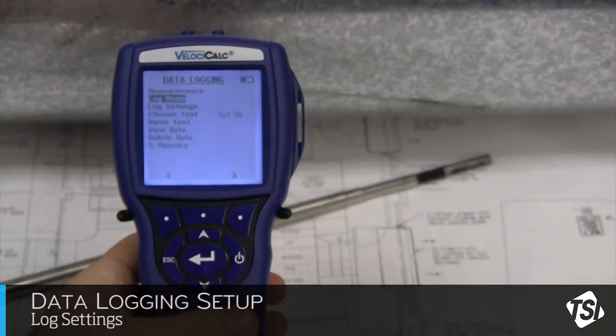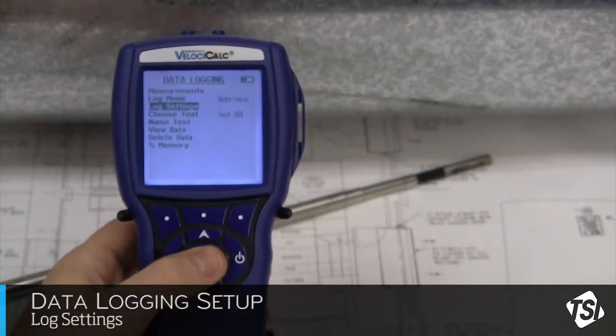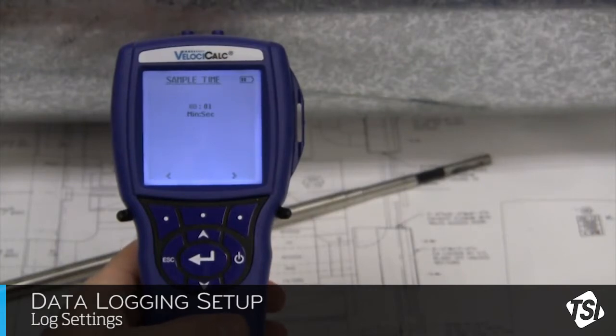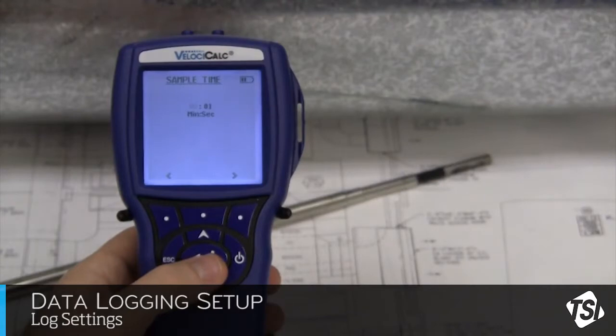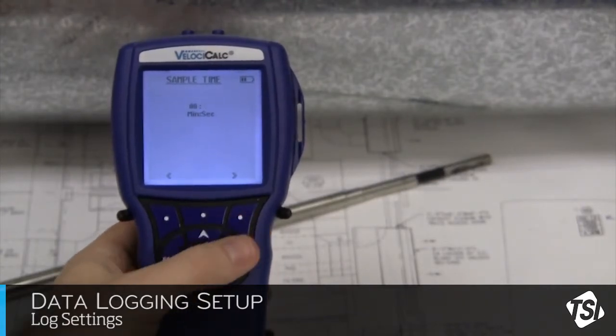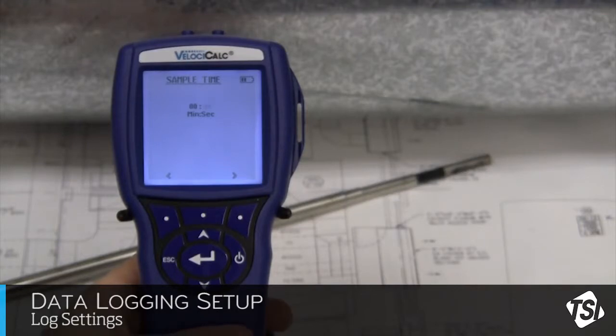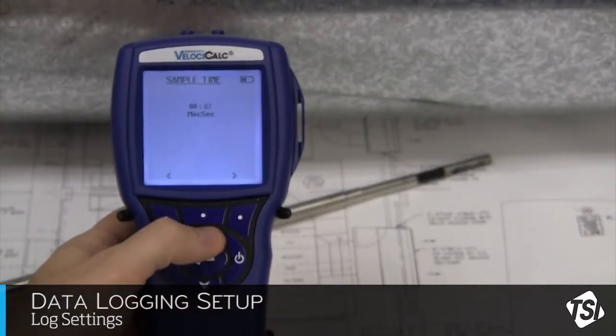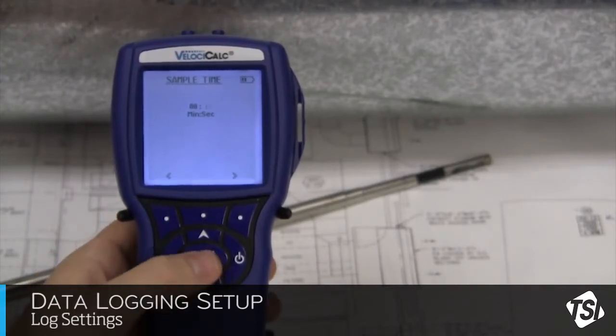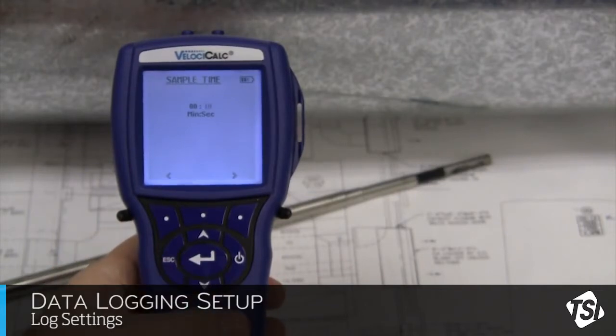Scroll down and highlight Log Settings and press Enter. We need to select the sample time. This is how long the unit will take a reading at any given point, and in the end, log the average for that reading. If you have turbulent airflow, having a longer sample time can help to average it out. In my case, I will choose 10 seconds. But just know that this may need to be adjusted according to your specific conditions. Change the sample time using the up and down arrows, selecting the minutes and seconds using the right and left soft keys. Once the appropriate sample time is selected, press Enter to save these changes.